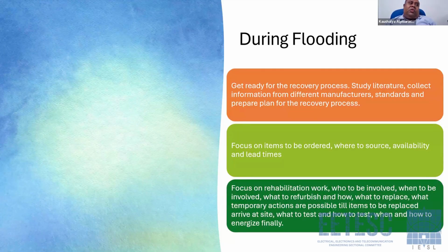Next thing, now you know you are submerged. Some items have submerged, some have partially submerged, and try to find sources. Where to source those? What are the availability of items and possible lead times? Because this will be very crucial to set up your flooded facility back on live, because the availability and the lead times are crucial. The demand may be very high because similar incidents might have happened for other places.